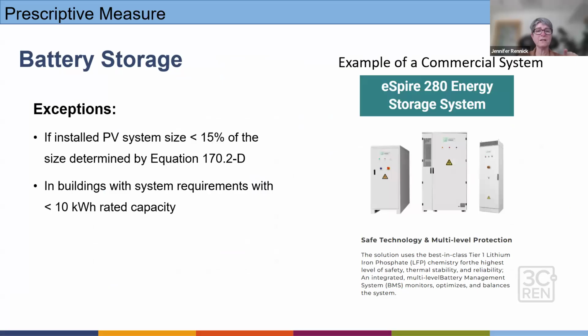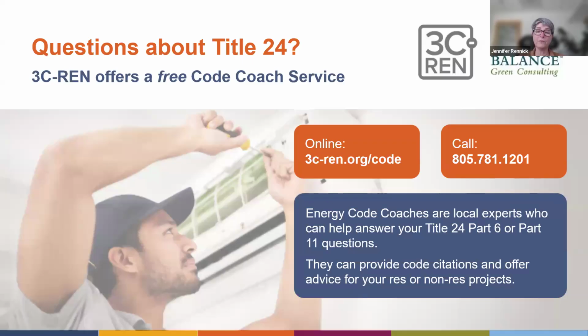And we still have the exceptions: if your PV system size installed is less than 15% of that size determined in the PV equation, or if the system requirements for that battery are less than 10 kWh rated usable capacity. And with that, we can help you figure out your Code Coach questions, and we can help you with crunching those numbers if you need it on your PV and battery as part of the Code Coach service.